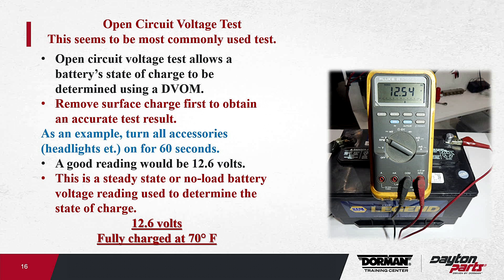And I'm always surprised, once you get down to around 12.5 or so, how rapidly the state of charge has dropped in relation to that, down to 75%. Most of the time, you put them on most batteries, chances are pretty good that's what you're going to wind up with, 12.54, till you give it a quick charge.